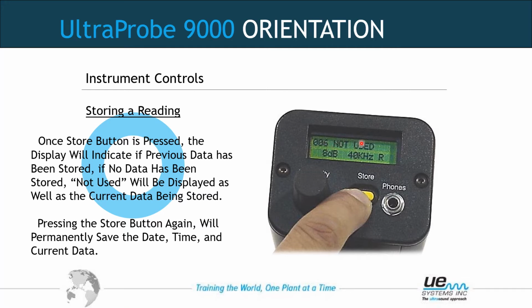So 006 not used. If it had been used, if we turn the dial backwards, we can adjust where we store it right now. That would be highlighted in black. The colors would be inverted on the number. You can store over a previous reading if need be. Otherwise, this spot has not been used, and we can store to this record location 006. The decibel was 8 dB, 40 kilohertz in a real-time mode. We will go over the different modes of the gun during this tutorial.